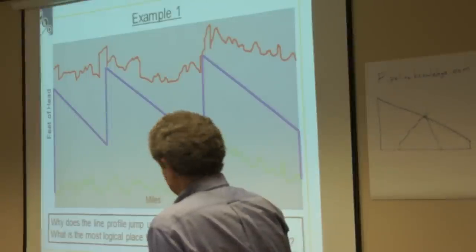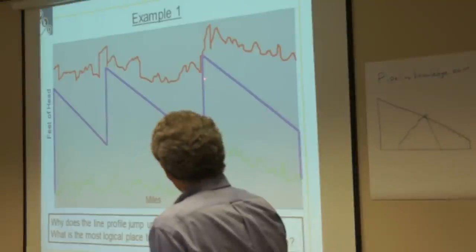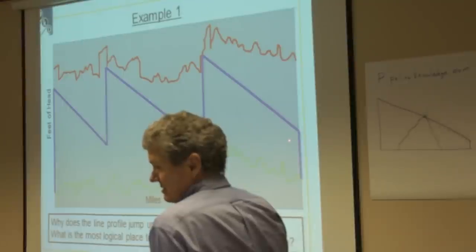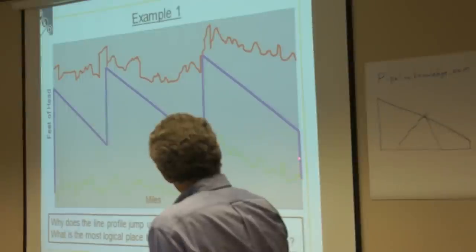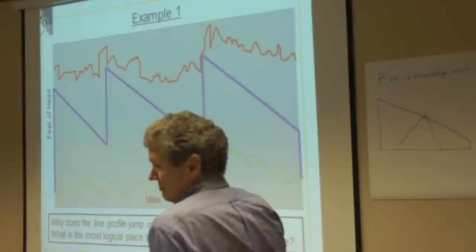At your third pump station, because it's all downhill from there. Basically, it's all downhill. So you'd look at what? After the last pump. Once you get over that hill right there, you're going to run downhill from there. Good. So why are you holding this much back pressure here? Because this back pressure is what's causing you to go there. If you weren't holding that much back pressure and only had enough to get over that last hill, you could come all the way down there, right? Or you might be able to drop this down there. Yeah, so that's the first place you'd look.